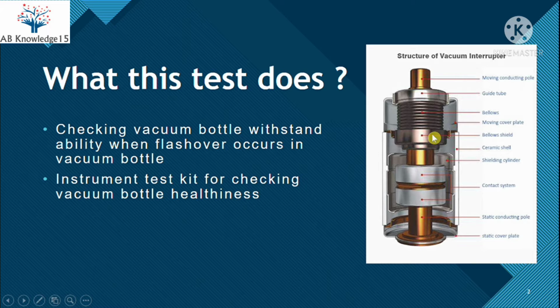Whenever any contact separation, pole separation or joining is done, flashover occurs in the vacuum bottle, and due to the vacuum the flashover is quenched in the bottle. So this test checks the withstand ability of a vacuum bottle, whether it is healthy or not healthy for continued operation. For this test there is a test kit for checking the vacuum bottle healthiness. Different types and makes of kit are available for this test.